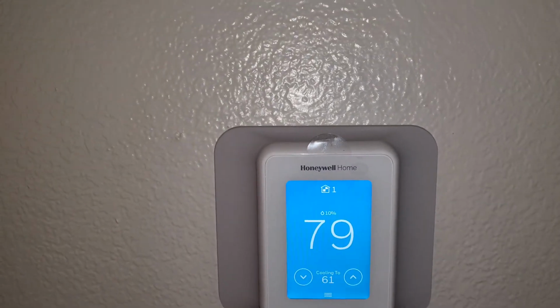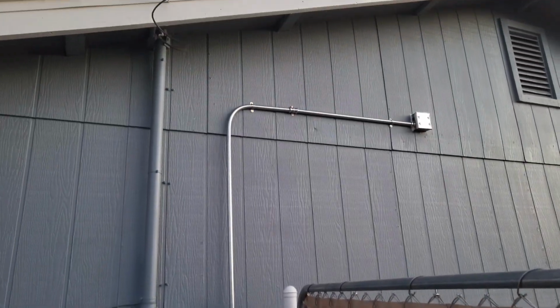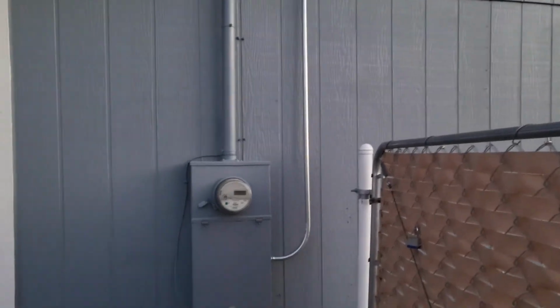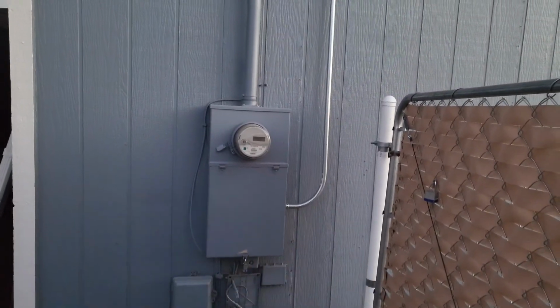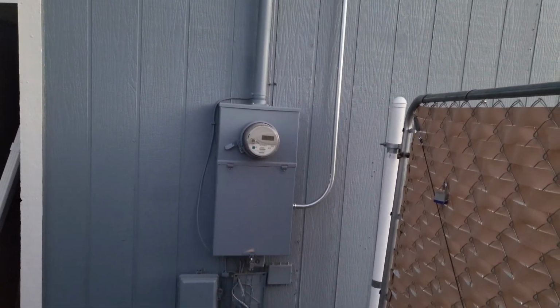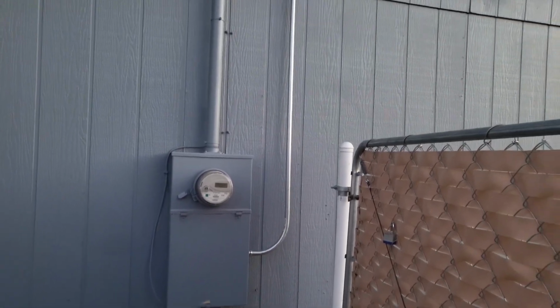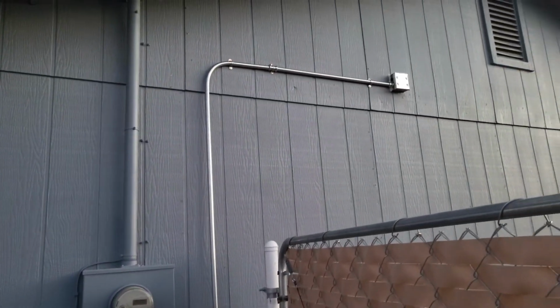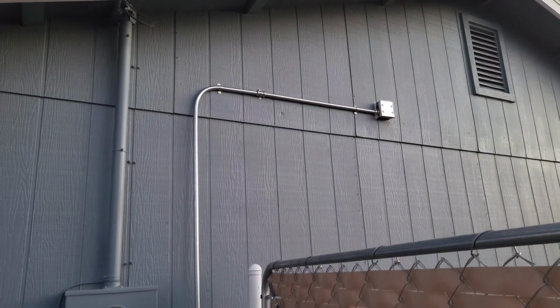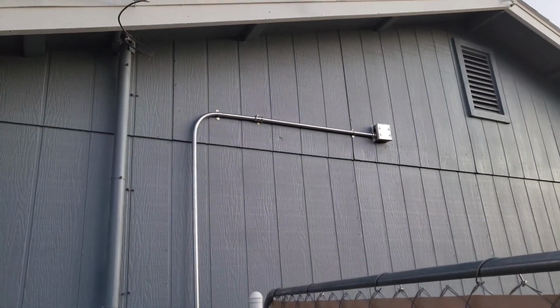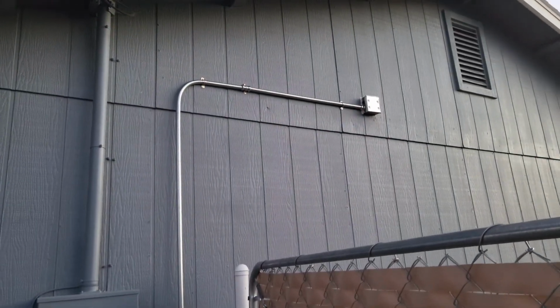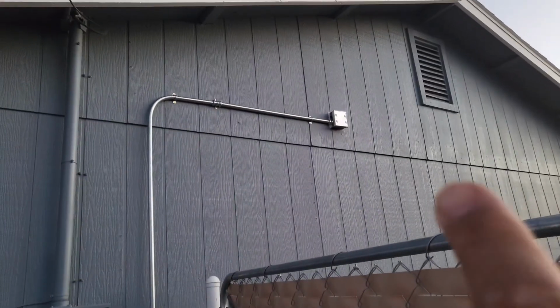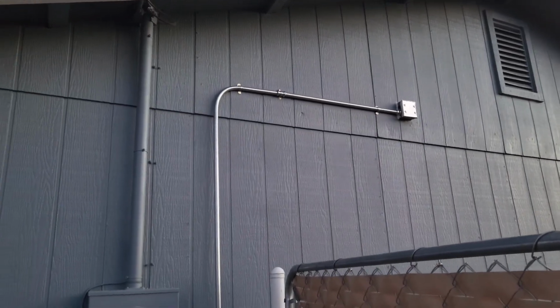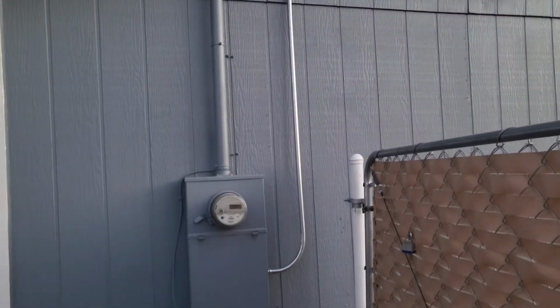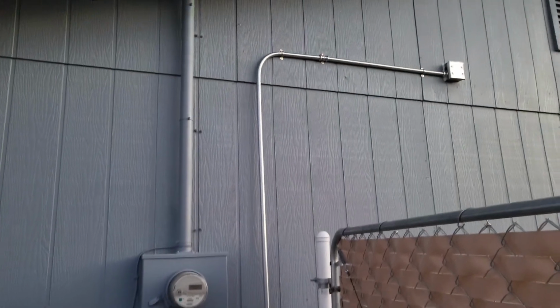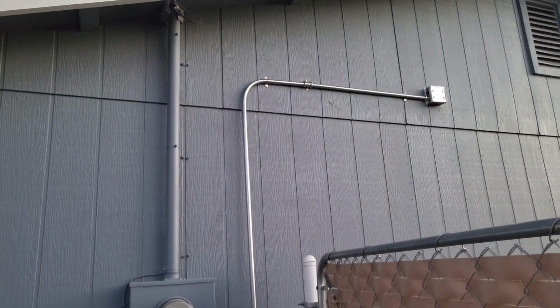So that's an option, and this is the electrical that I had to do, right? So inside of the box, I put in a new breaker, ran the high voltage, bent the conduit. Nice. I bent the conduit, put on a weatherproof box, and the high voltage goes to the new system, because remember, nothing was really installed in this home.